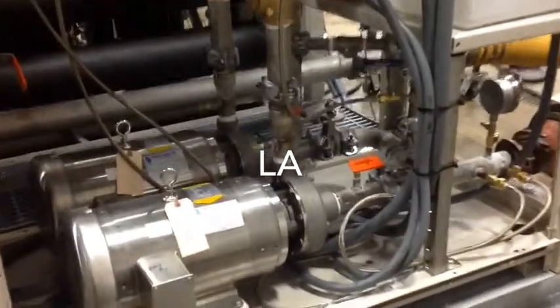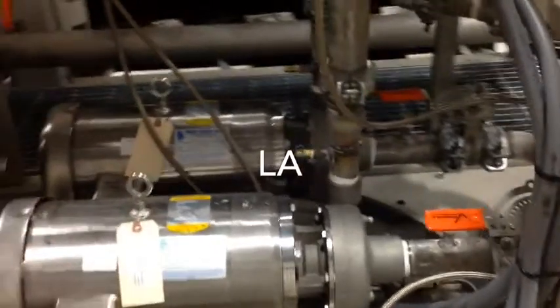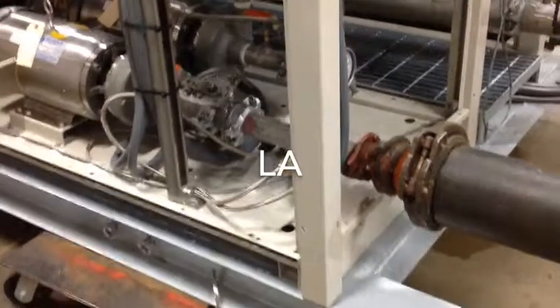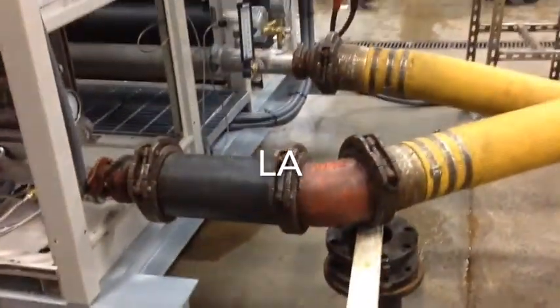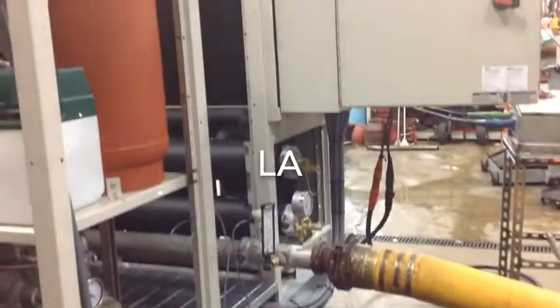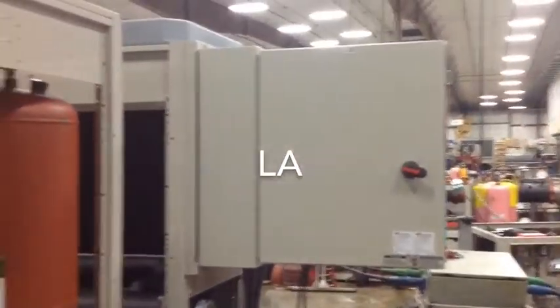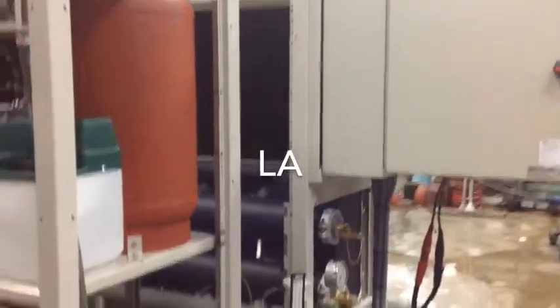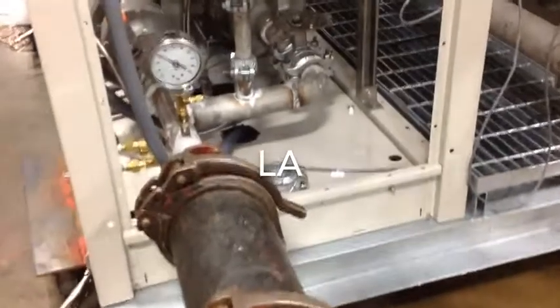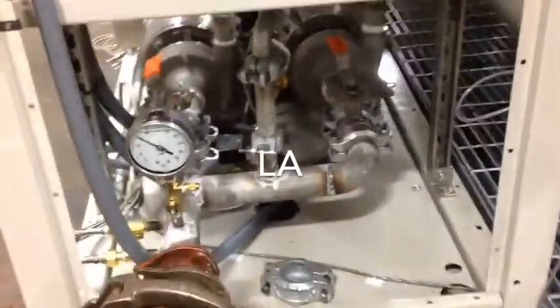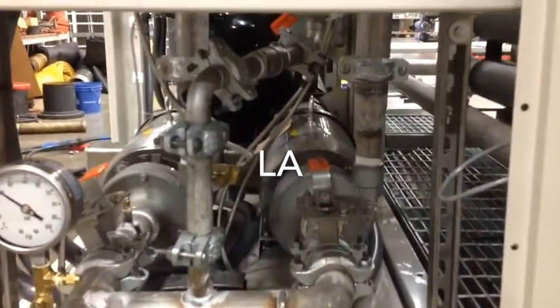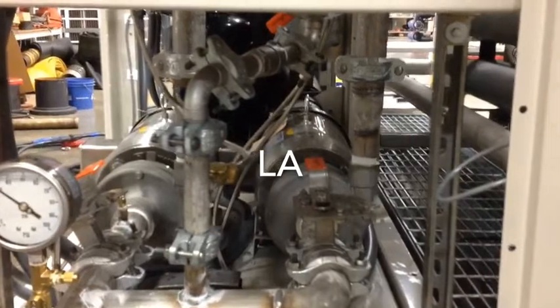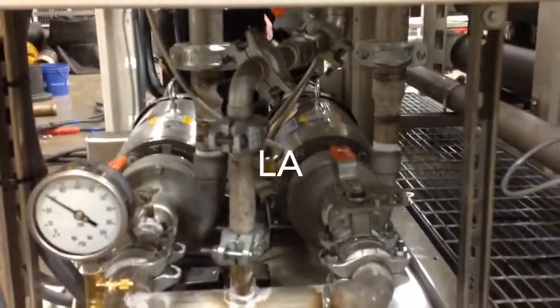And now we'll swing around to the right to see the entering connection, which is down there at the lower right. You just saw it with the pressure gauge right here. And then the leaving connection is on the background of the picture there. And there's the leaving connection with thermometer, pressure gauge. Down laying in the base of the pump module, you'll see the galvanized coupling for the entering connection. So that will ship connected to the chiller for use by Thermal Dynamics in connecting their field piping.